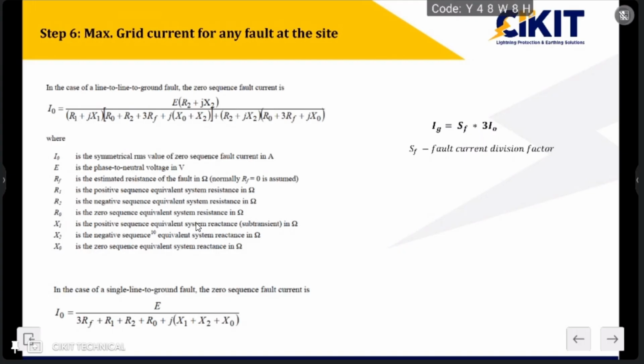So if I have a substation with a lot of feeders, let us say this is a substation and we have towers here, and on top of the tower we have this ground wire. Similarly, here also we have towers. Here we have this equipment, and we are burying the earth mat. If some fault happens, some current will return to the source through the soil, and some portion of the current may return to the source through the transmission line ground wire. So some portion of current is diverted to the source through the shield wire or ground wire. The entire current won't be flowing through the soil. Some portion of the current will be flowing through the transmission line ground wire, and the remaining will be flowing through the soil.